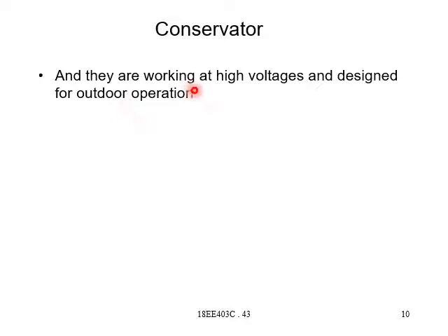These conservators work at high voltages. That means they are for power transformers, not for smaller ones. There is no need for conservator tanks for smaller transformers like distribution transformers. They are designed for outdoor operation. You may have seen outdoor substations and indoor substations. These conservators have a huge structure, and they are used for outdoor operation.